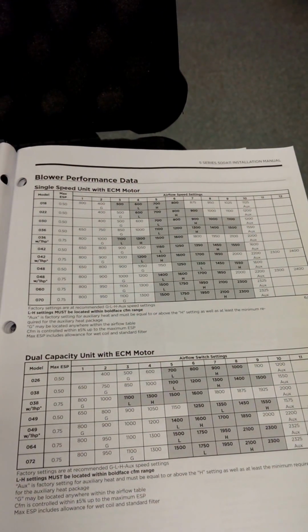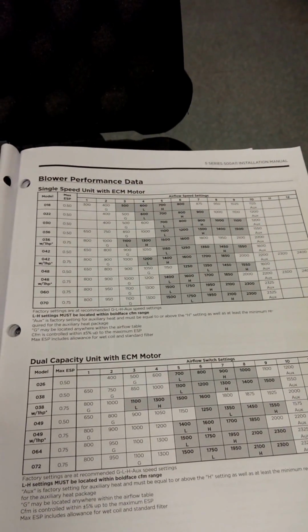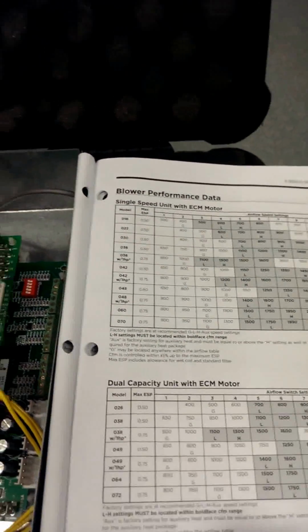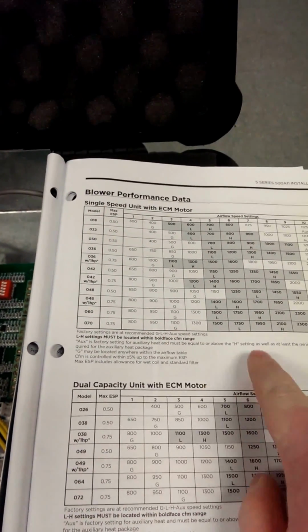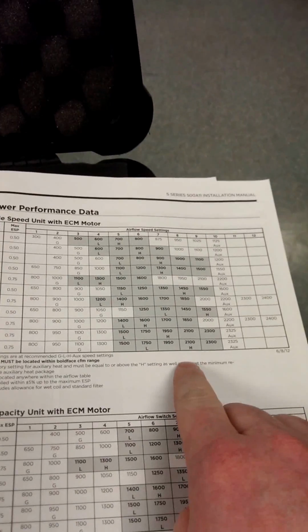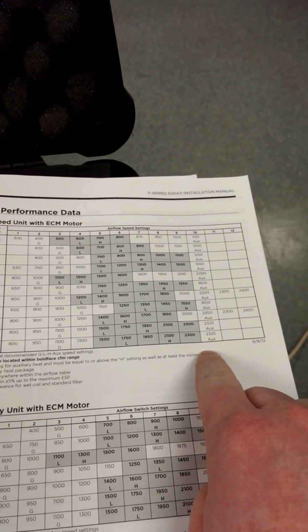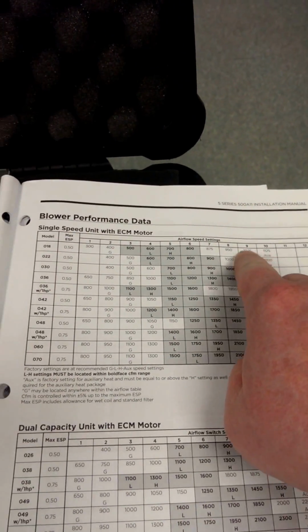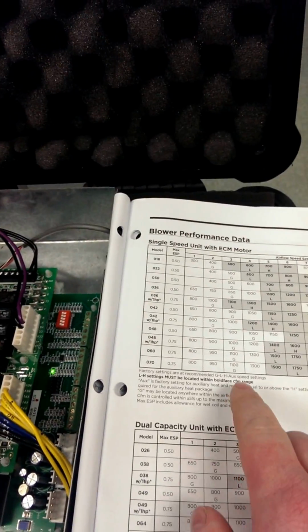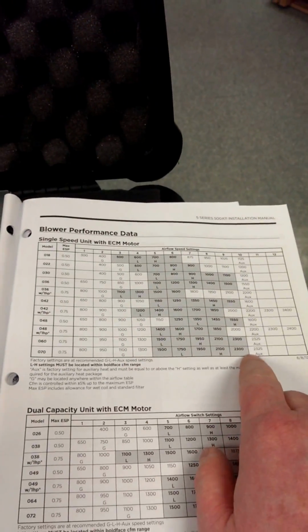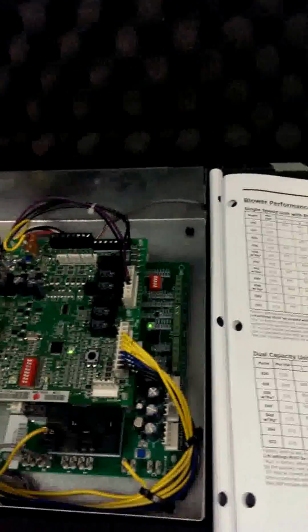So if you look at the blower performance data that comes with your unit, you'll notice if this was, for example, an 070 unit, they have a recommended G, a recommended low speed, a recommended high speed, and a recommended auxiliary heat, and then above that is a number that corresponds with it. You can obviously pick within the ranges on all of these numbers. To set it up with the aid tool is quite easy.